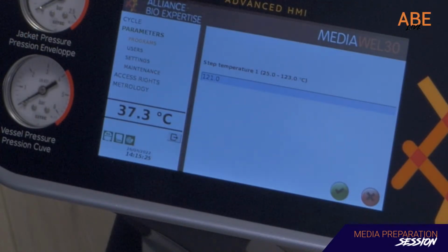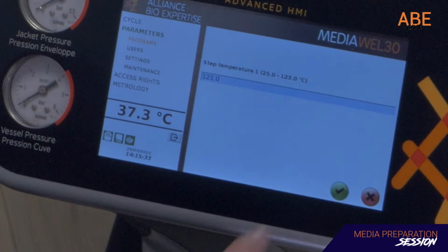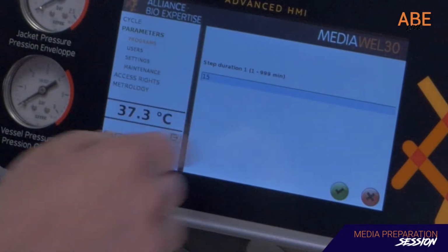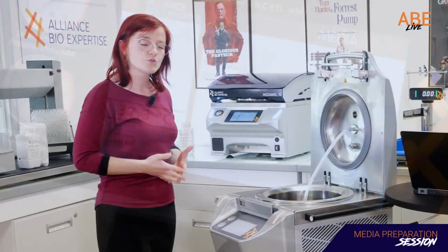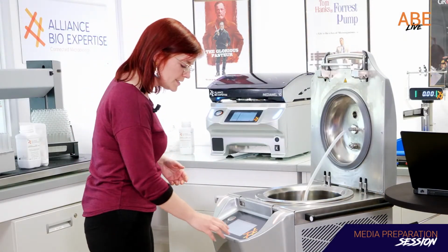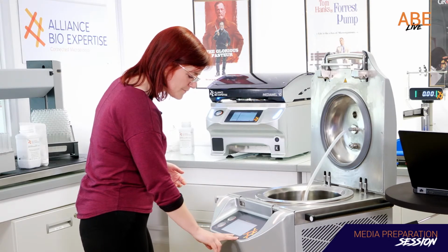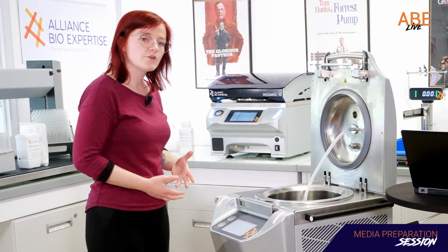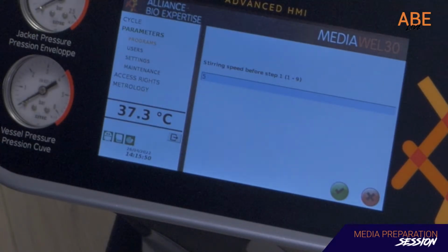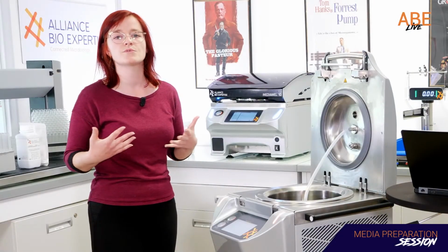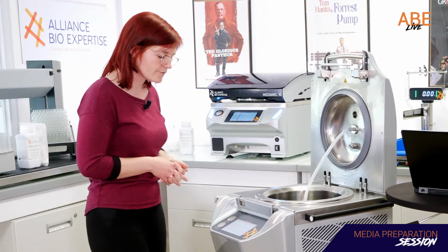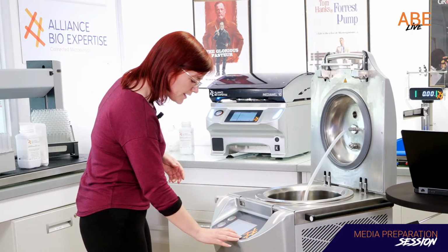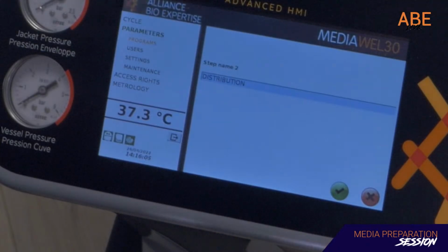Because we are on sterilization 1, we'll go for 121. But you can notice that here you can go up to 123 if needed, according to your different protocols. Then you have the duration of the step. So usually 121 degrees during 15 minutes, that you can also adjust if necessary. And then it will ask for the speed during and before the step, so it means the speed of the stirring system. Again, you have pre-filled information that goes okay for 95% of the media, otherwise we can adjust. But here we will keep on with the one we have here.